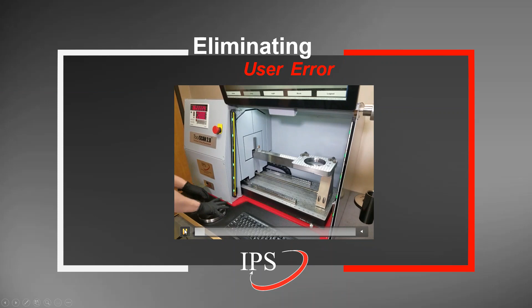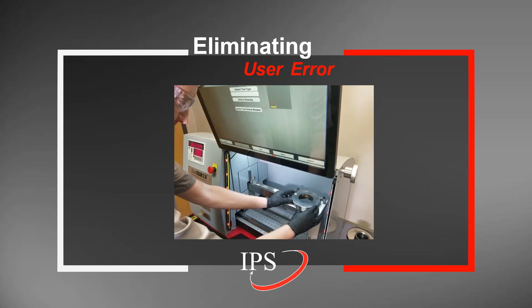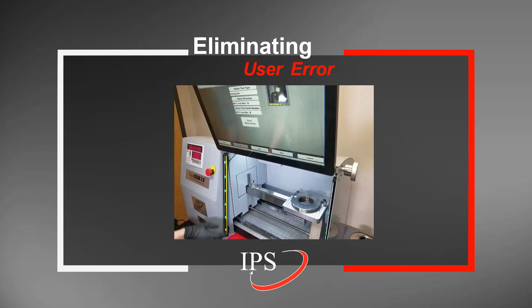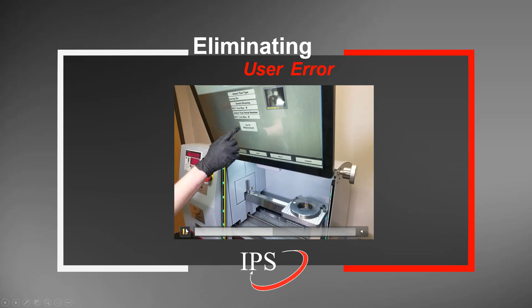In this video, a die is placed inside the gauge, and at this point they scan the barcode that is on the die itself. By that quick scan, it pulls up the correct tool profile: the tool type, a die, the serial number, and the correct calibration group, so that the most accurate measurement possible is performed. So a quick scan, and then go is pressed.